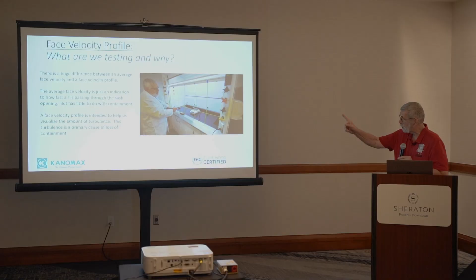So one of the things that a lot of people don't really understand is that there's something in ASHRAE 110 called a face velocity profile. And what they do, as you can see in the graphic, they divide the face of the hood off into roughly 1 square foot squares. And then you go and you do readings in each of those squares. And what you want is you want those values to be pretty flat. And we're going to look at that here in just a second.